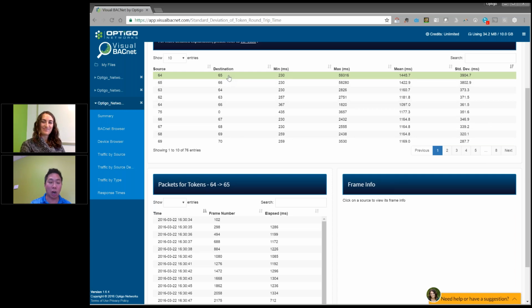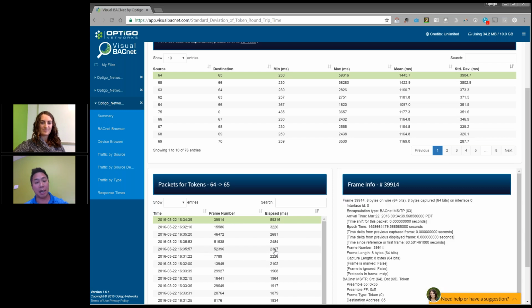If you click on that, it shows the frame, which again correlates to the Wireshark capture that actually did the passing of tokens from device 64 to 65. The interesting thing is if you click on elapsed and sort by max, you can see that the last time 64 successfully passed to 65 was nearly a minute ago.